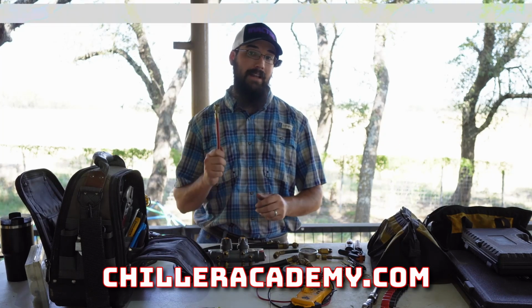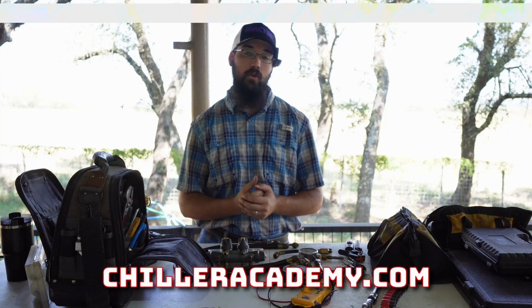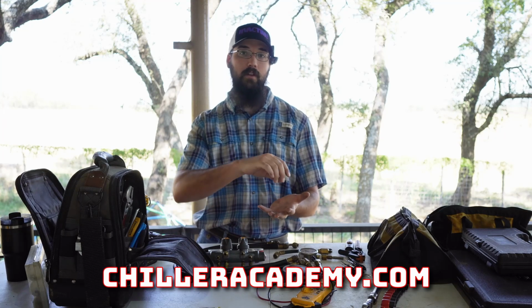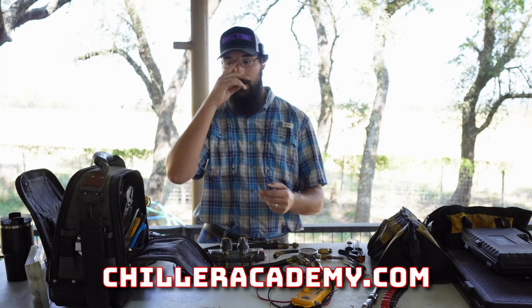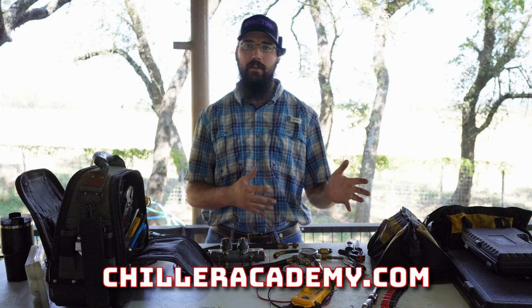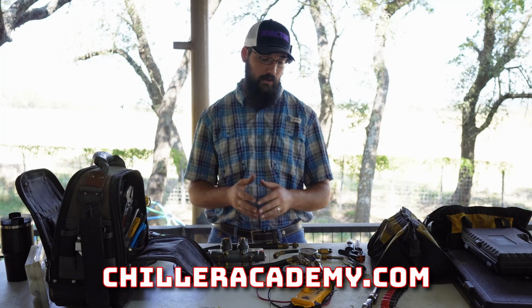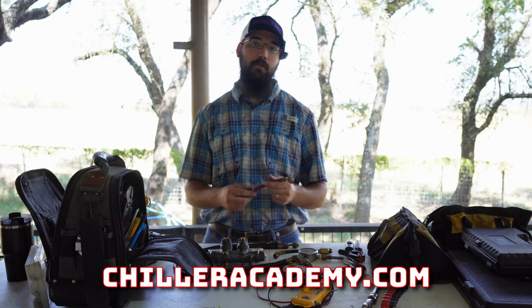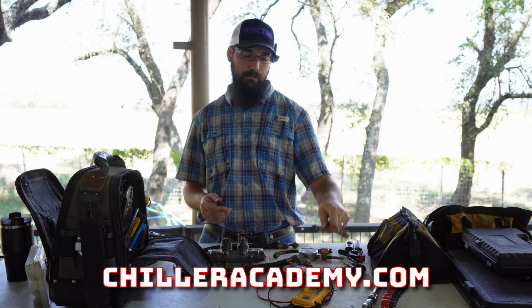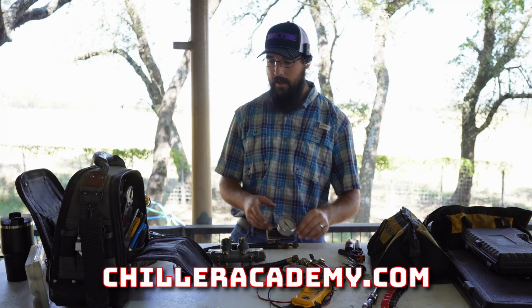So if I had something where I needed to use a depressor, I did one of two things. I either put my stubby on there, or I used a core tool and just pulled that core completely out of the way, and then I would use the core tool itself as my isolation valve from there. So just depending on what my circumstances were, depending on which way I needed to go with it. If I was actually trying to transfer from the machine to a tank or vice versa, I would pull the core. If all I am doing is just trying to get a pressure reading temporarily, I don't need to pull the core for that. I can just use a depressor. So just to kind of paint a picture as to which direction I would go depending on the circumstance.